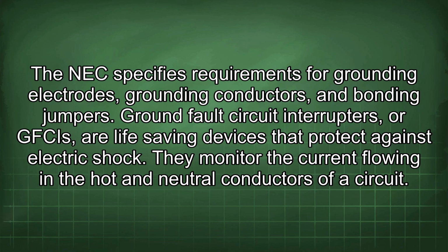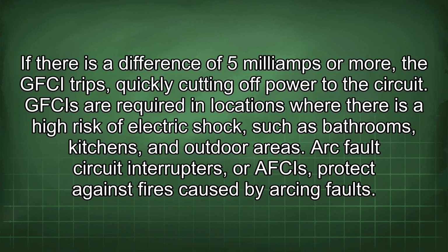Ground fault circuit interrupters, or GFCIs, are life-saving devices that protect against electric shock. They monitor the current flowing in the hot and neutral conductors of a circuit. If there is a difference of 5 mA or more, the GFCI trips, quickly cutting off power to the circuit. GFCIs are required in locations where there is a high risk of electric shock, such as bathrooms, kitchens, and outdoor areas.